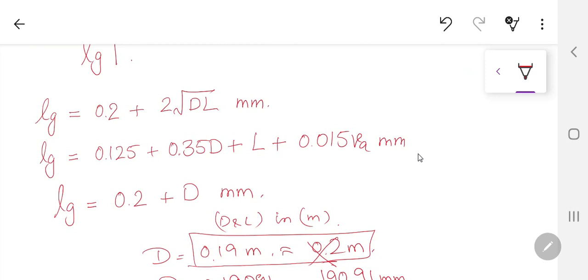You may be asked to just make a 3 mm air gap length, and 3 mm is so small that when it goes into manufacturing, sometimes the stator hits the rotor or something like that happens, and you are damaging the machine. So it is very important that air gap length is a value where you take into consideration your mechanical problems and how much precision you can have in balancing the rotor exactly at the center of the stator.